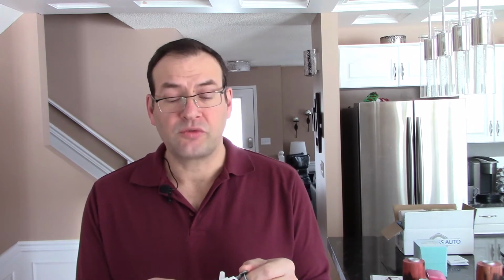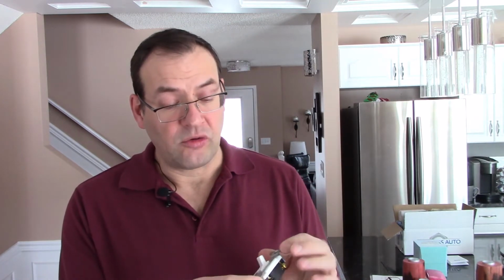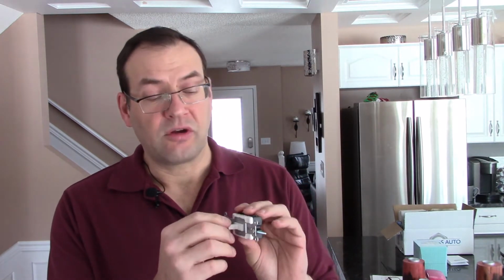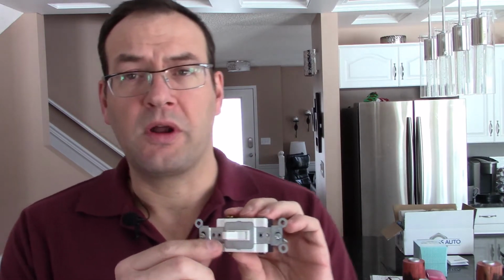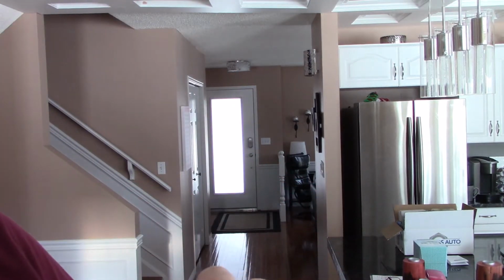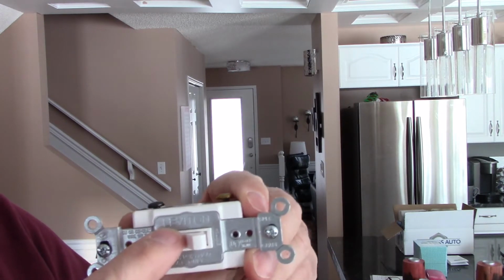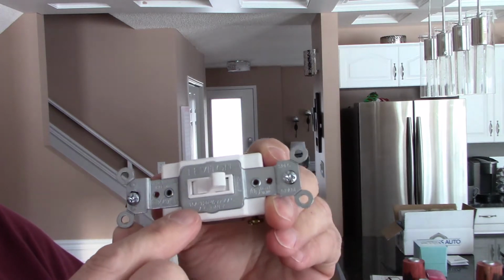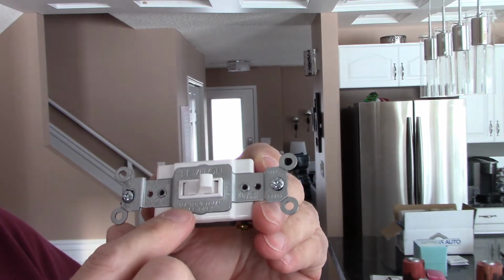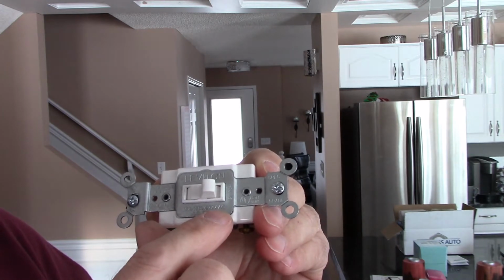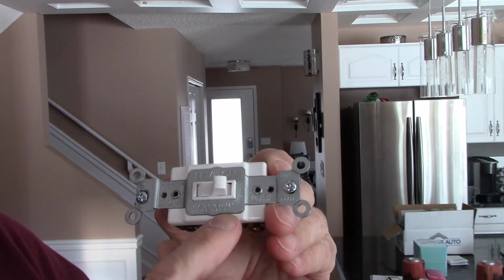The first thing to know about a switch is whether the switch you're using is rated for the application you're putting it in. Most residential applications, you need a 15 amp switch. When you have a switch in your hand, you'll be able to see what it's rated for because it's always printed on the switch itself. If you see this one, you can see it's upside down here, the manufacturer. You can see the amperage, 15 amp, 120 volt, 277 volts, AC only.